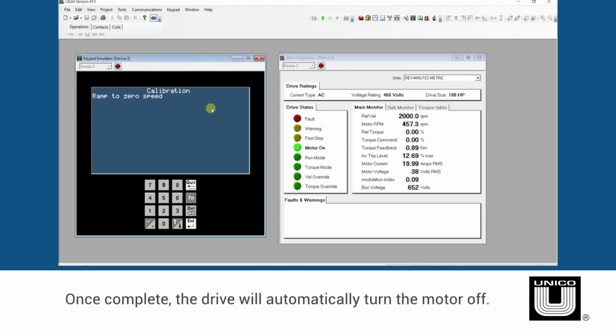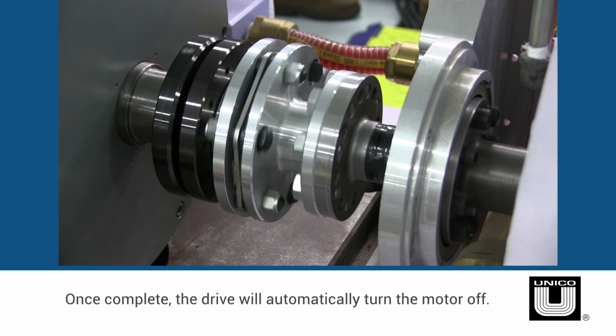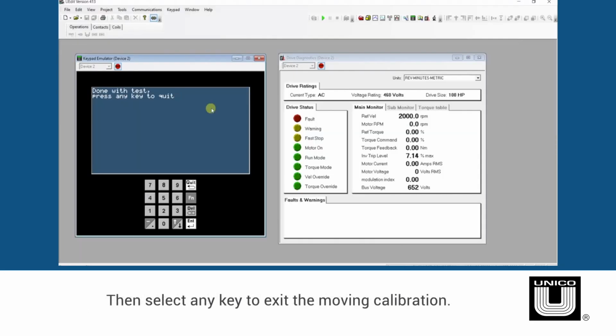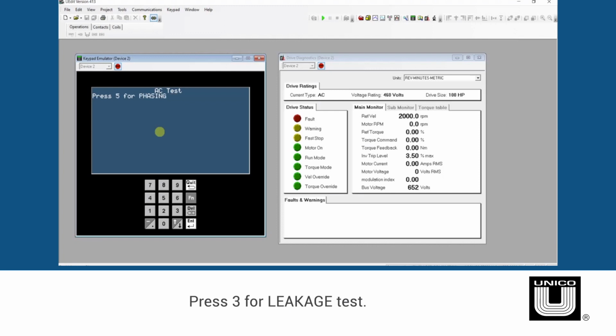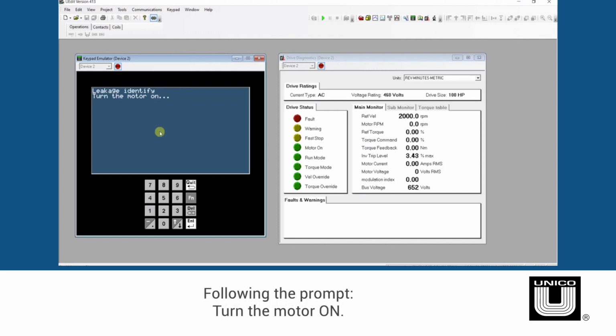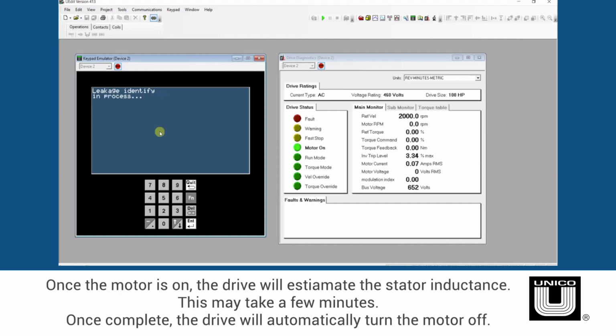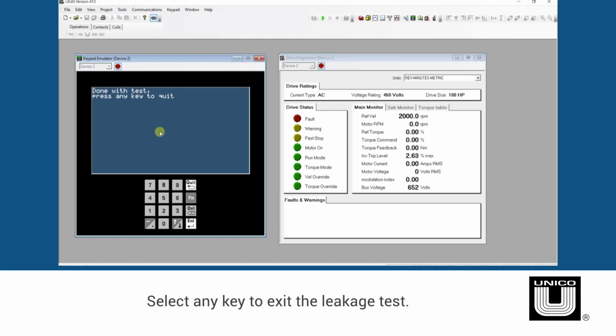Once complete, the drive will automatically turn the motor off. Then follow the prompts and select any key to exit out of the moving calibration. Next, select 3 for the leakage test. Once the motor is on, the drive will estimate the stator inductance. Again, select any key to exit the leakage test. Next, select 4 for the stator resistance test.